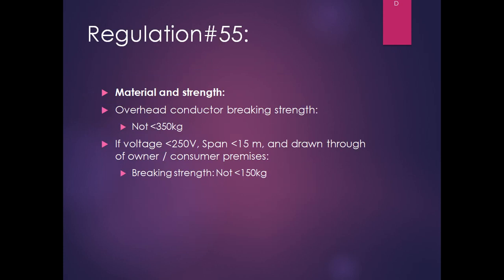Regulation 55 is regarding material and strength. Overhead conductor breaking strength shall not be less than 350 kg. However, if your voltage is not exceeding 250 volt, the span is not exceeding 15 meters, and the conductor is drawn through the premises of either the owner or consumer, you can use an overhead conductor whose breaking strength is not less than 150 kg. So if your voltage is low, your span is defined, and the conductor is laid either on the owner's or consumer's premises, you can use the lower breaking strength.